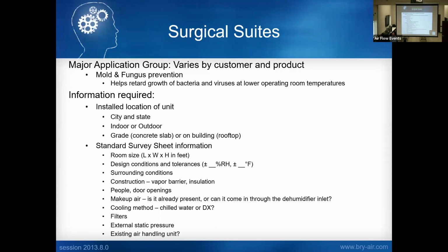If I'm dehumidifying this room, what's surrounding each wall? Is it outside air? Is it conditioned air? The construction of the room, people, door openings, makeup air, and cooling. On a typical surgical suite, especially in a hospital, they probably already have a chilled water plant and hot water, so you simply want to use that. Sometimes we may need DX. Filtration required, and external static pressure if there's an existing air handler.